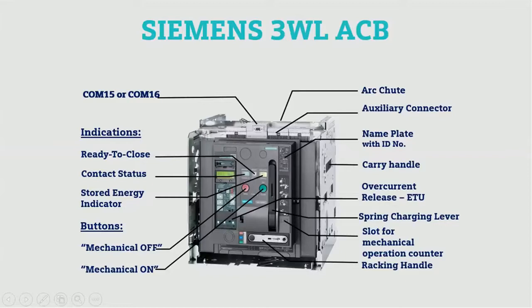There is an electronic trip unit for configuration of the ACB, and an LCD display that provides technical information. On the upper side there is a communication port where Profibus or Modbus communication is possible. On the back side there is an arc chute and auxiliary contacts. A handle is provided for dragging the ACB out from the rack, along with a slot for a mechanical operation counter and the ETU.